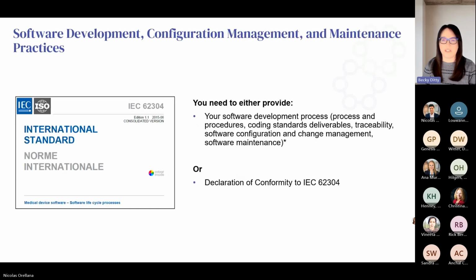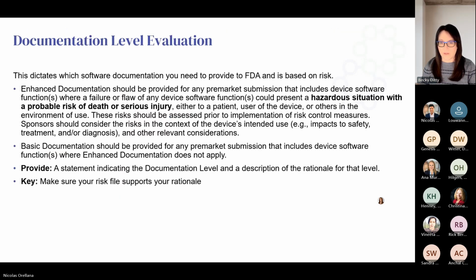As we talked about, the first thing you're going to want to do is set up your software development process, and you're going to want to use the IEC 62304 to do that. This standard will give you 90% of what you need for your software submission. FDA has a couple items in the guidance document that you're going to be specifically developing for the submission that are outside of IEC 62304. And we'll talk about those in a moment.